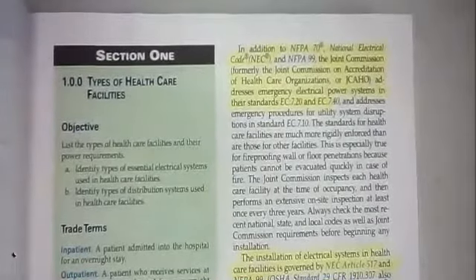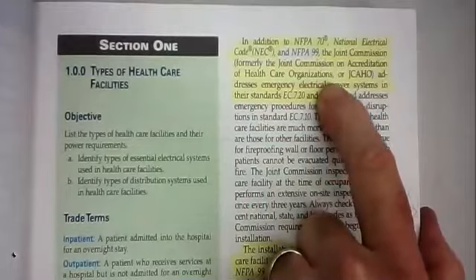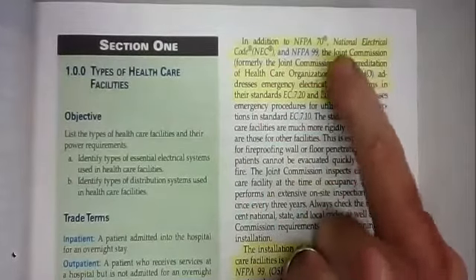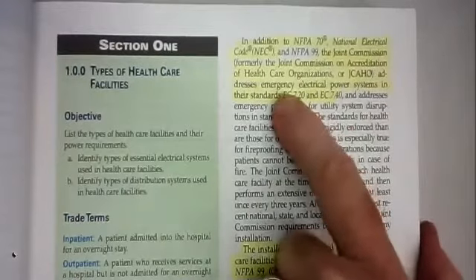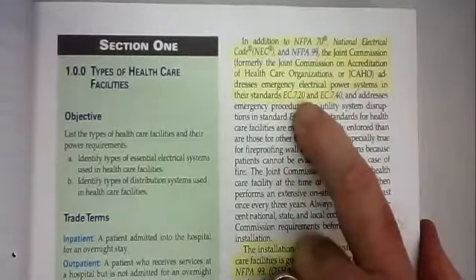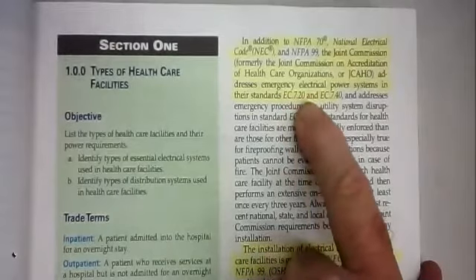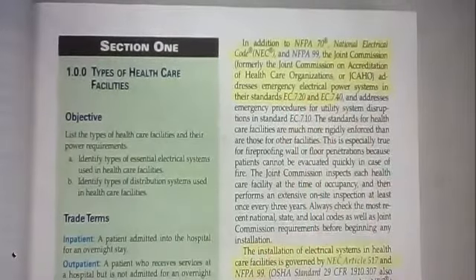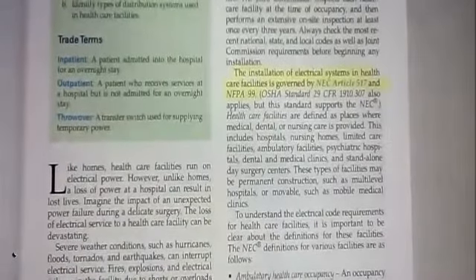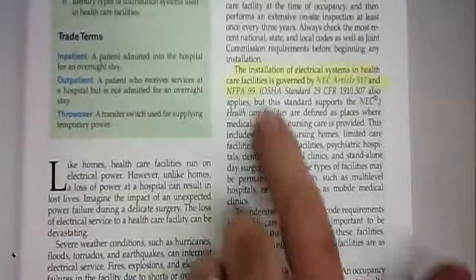On the right-hand column of page 1, it says, in addition to the National Fire Protection Association 70, that's the National Electrical Code, and NFPA 99, the Joint Commission, formerly known as the Joint Commission on Accreditation of Healthcare Organizations, JCAHO. Now they just call it the Joint Commission, period. It addresses emergency electrical power systems and their standards, EC 7.20 and EC 7.40. So the Joint Commission.